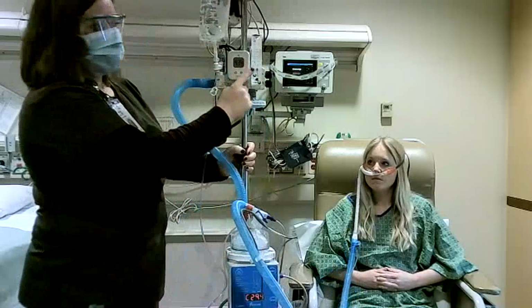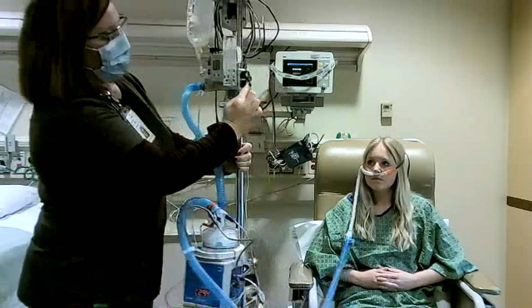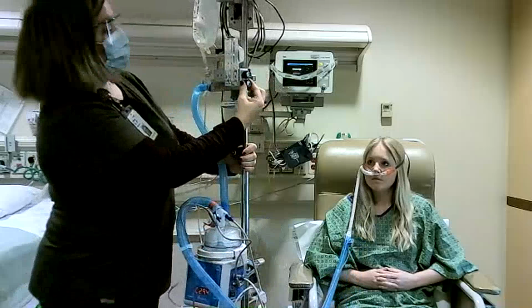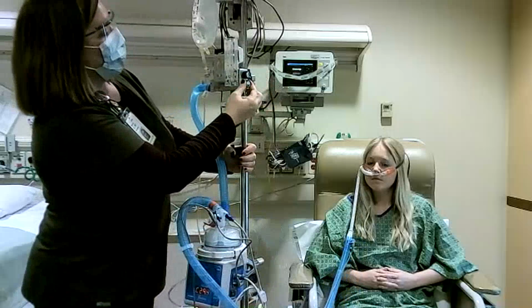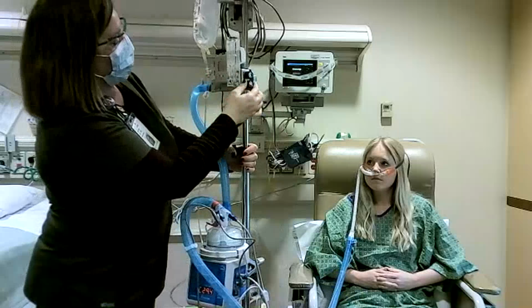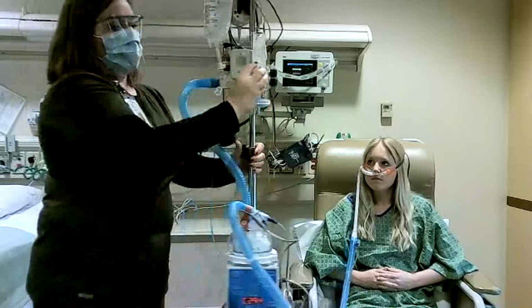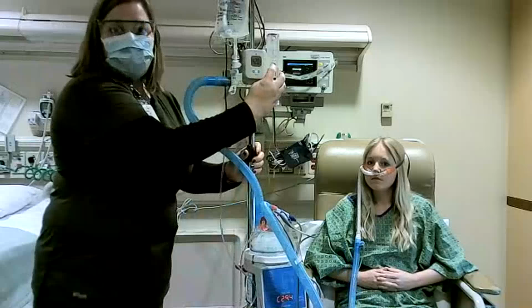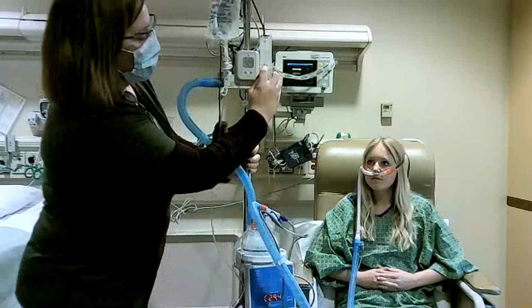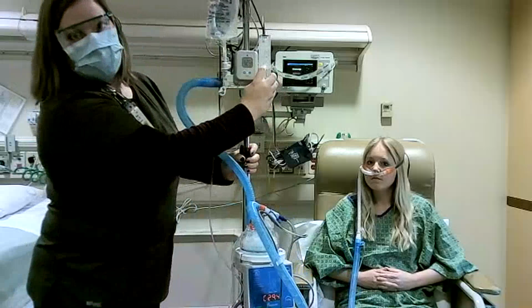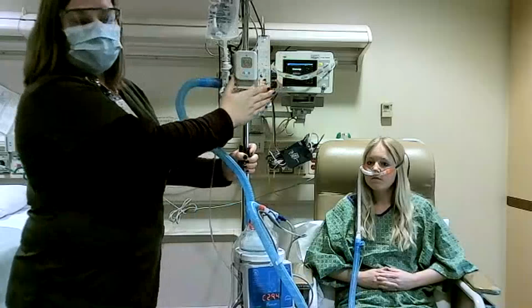We're currently at 30. We're going to go down to 25. So we're going to go to our bottom knob. Again, dial it back, watching your ball here. You're going to want to line the center of the ball up with the line. So the center of the ball is lined up with 25. She's now on 25 liters per minute, which is where we want her to be, and we're going to continue to monitor her.